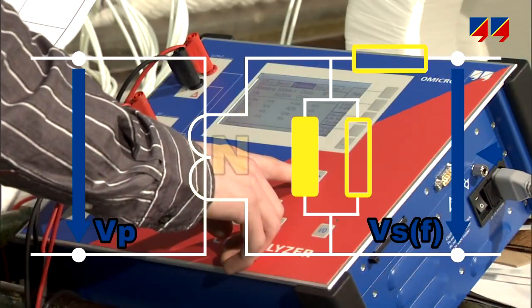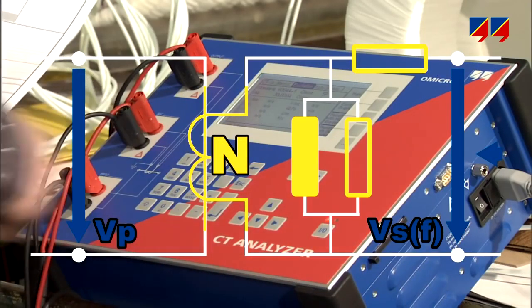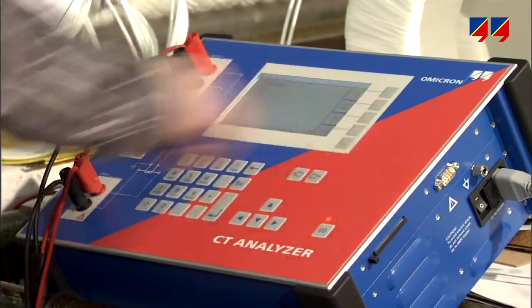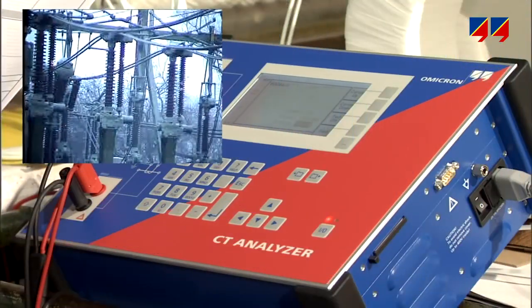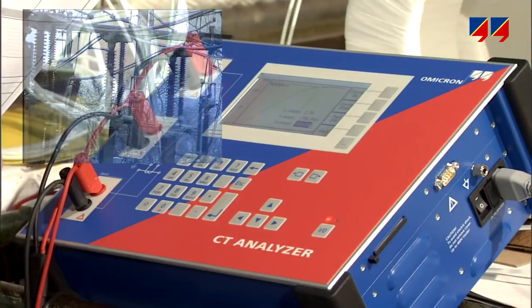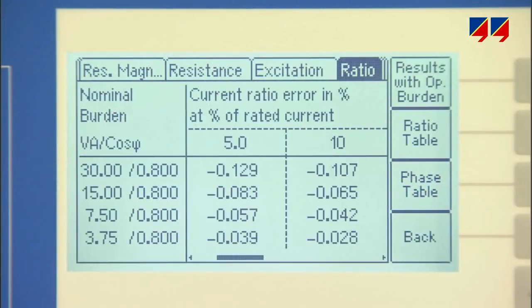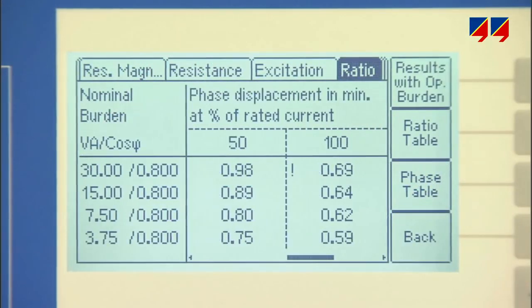Finally, it measures the turns ratio with variable frequency injection and frequency-selective measurements, unaffected by external noise. Based on these measurements, it determines the accuracy data for all defined current and burden value combinations.